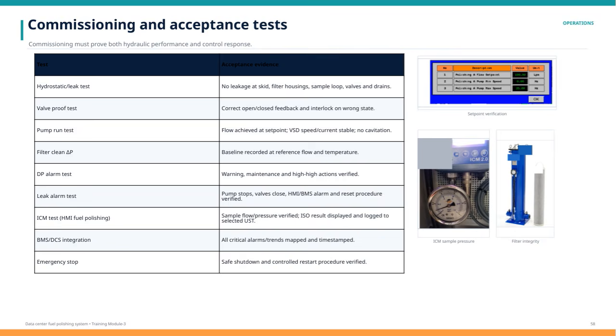The integrated control module test for fuel polishing verifies sample flow and pressure, and confirms that ISO cleanliness results are displayed and logged correctly. When it comes to system integration, all critical alarms and trends must be properly mapped and time-stamped within the building management system or distributed control system. Finally, the emergency stop test assures a safe shutdown and a controlled restart, ensuring the whole system handles emergency situations smoothly. Through these thorough checks, we can confidently verify set points, monitor sample pressure, confirm filter integrity, and ensure the fuel polishing system operates safely and efficiently.